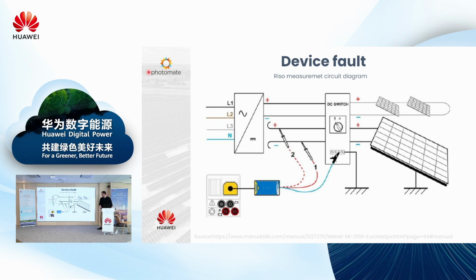When you connect the DC voltage meter between the positive pole and ground, you will see the voltage slightly decreasing through time. This means it's discharging through the internal resistance of your multimeter and everything is fine. But if not, you will see many different strange behaviors, like the voltage going up and down, or not being stable. In that case, you might have a problem with the isolation. But it's always better to use the isolation multimeter.